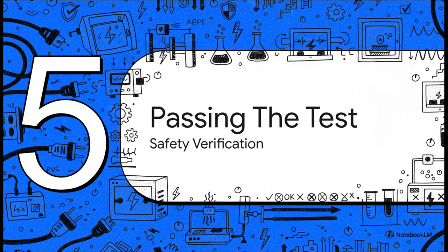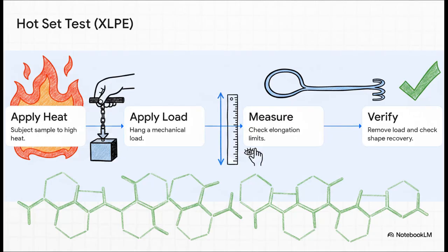Which brings us to our final stop, Section 5, Passing the Test. Before any of these cables are allowed anywhere near a live power grid or your home, they have to prove their worth in the laboratory. One of the most fascinating verifications they do is the hot set test, and this is uniquely for XLPE. This test physically proves that the crucial chemical cross-linking process was actually a success. First, they apply high heat to a sample. Second, they hang a heavy mechanical load from it. Third, they measure exactly how far it stretches. It absolutely must stay within strict elongation limits. And finally, they remove the load, and the material has to snap back and completely recover its shape. If it doesn't, the whole batch fails.